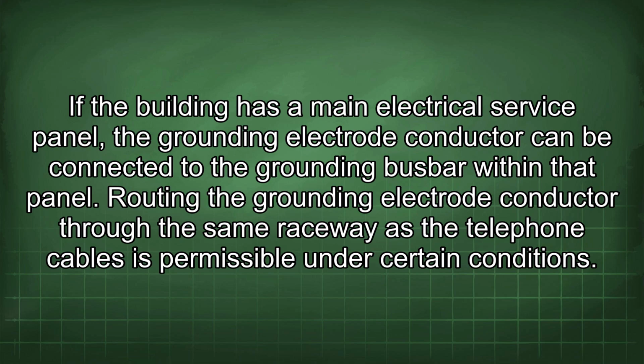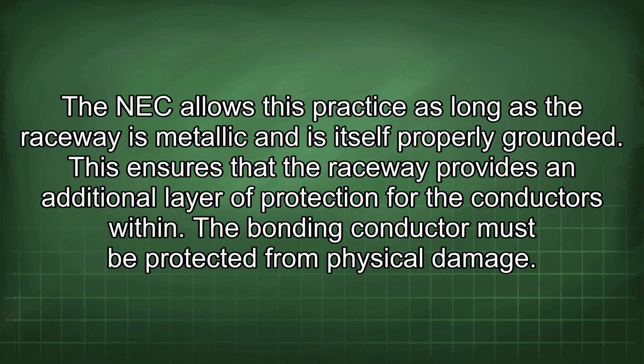If the building has a main electrical service panel, the grounding electrode conductor can be connected to the grounding busbar within that panel. Routing the grounding electrode conductor through the same raceway as the telephone cables is permissible under certain conditions. The NEC allows this practice as long as the raceway is metallic and is itself properly grounded. This ensures that the raceway provides an additional layer of protection for the conductors within.